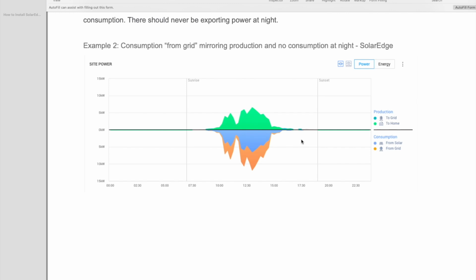So this right here is a clear sign of a CT error. In most cases, this is phase alignment, when you have the CTs on the wrong phases. You have no consumption whatsoever until the sun comes up, and when it comes up, consumption is double production. This is one form of what we call mirroring. So again, you should have some amount of consumption at night, and you should never have consumption mirroring production.